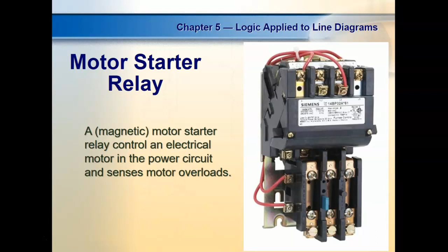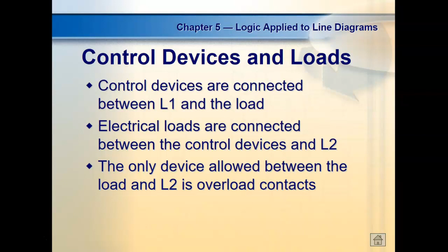Okay? Control devices and loads. So control devices are connected between L1 and the load. We've already said that. Electrical loads are connected between the control devices and L2. The only thing allowed between those devices of the load and L2 are overloads. It's the only thing you're supposed to put in there. And again, that's so that if you start passing excessive current, it's got some way of saying, I'm not doing that.